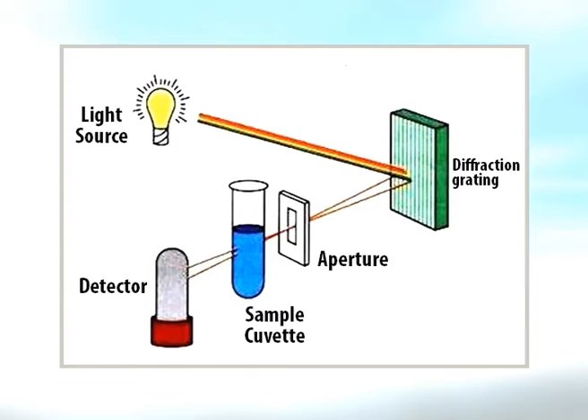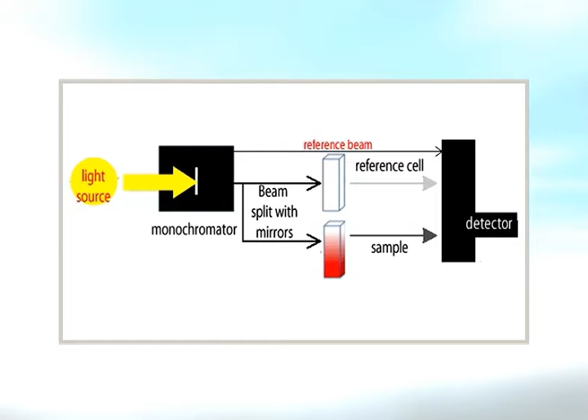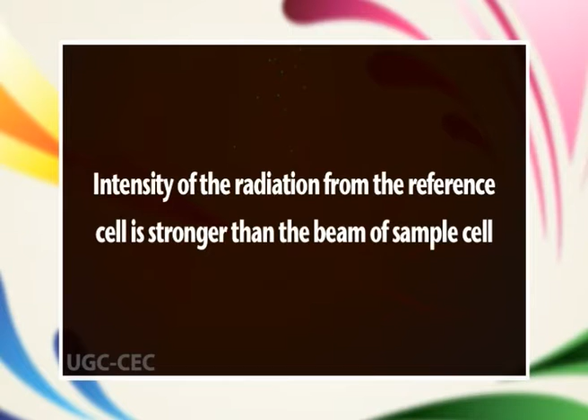Number 4 is the detector. Generally, two photocells serve the purpose of detector in UV spectroscopy. One of the photocells receives the beam from the sample cell and the second detector receives the beam from the reference. The intensity of the radiation from the reference cell is stronger than the beam of the sample cell. This results in the generation of pulsating or alternating currents in the photocells.